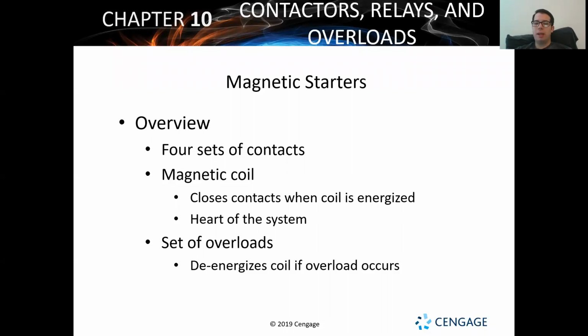but basically it's going to be a starting system for larger units. That's what you're going to see a magnetic starter used for a lot of times. It's not just going to be a contactor though, it's also going to have parts of it that will be like an overload device. So basically a contactor and an overload device made a baby, and that is a magnetic starter or a motor starter. That's what you're going to be seeing a lot of times for those.